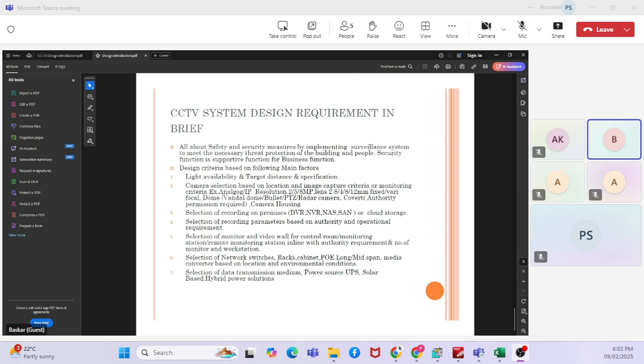And when we are choosing the power source, the UPS also has to be considered. There are regulations asking that it has to have a 30 minutes battery backup. So we have to choose how many switches are there for connecting the cameras. What is the load of the switch? Based on the switch load, we need to consider an additional 20% spare based on the local regulations. If it's 20% spare or 30% spare.